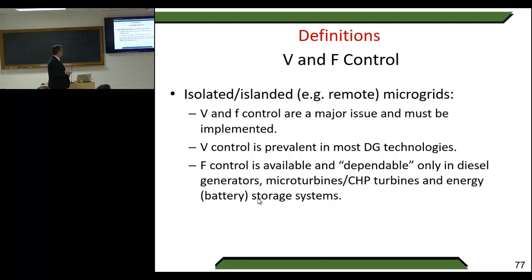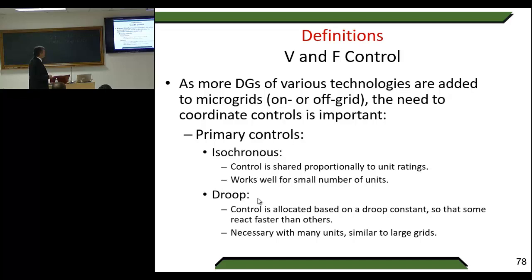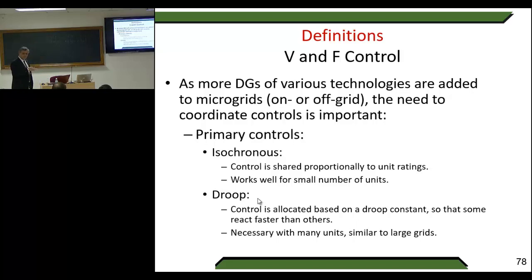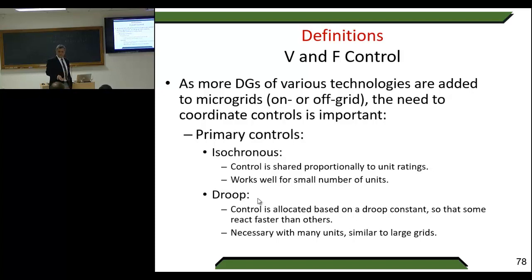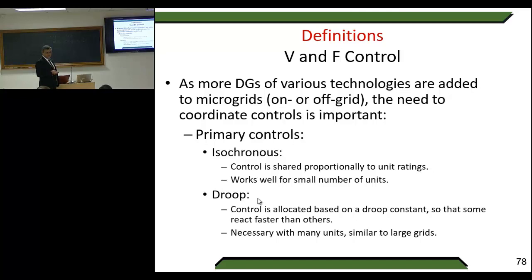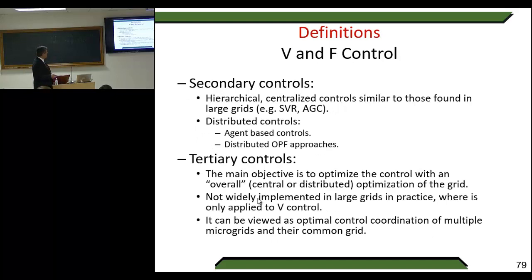Frequency control is not available for all DG technologies. As more DGs of various technologies are added to microgrids, the need to coordinate control is important. In primary control, you have isochronous mode or droop mode. Isochronous mode shares control proportionally to unit ratings; it works well for a small number of units but becomes complicated with more units as oscillations arise. Droop control allocates control based on droop constants so some react faster than others — similar to the strategy used in main systems.